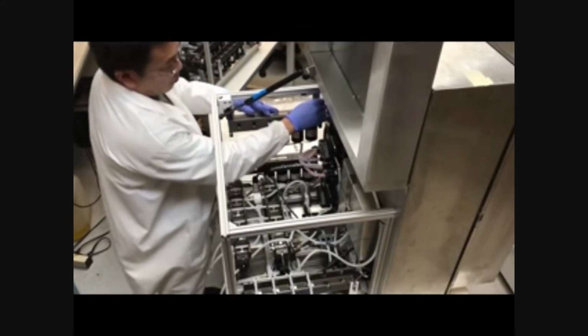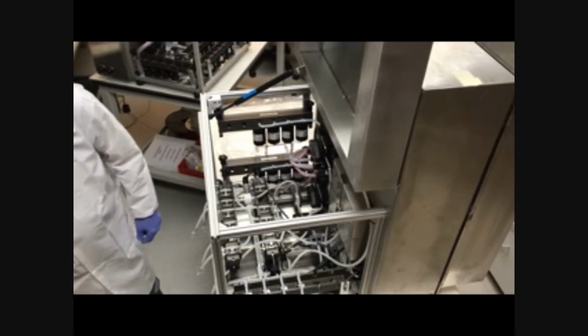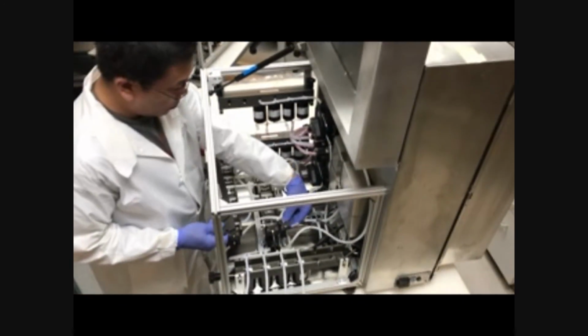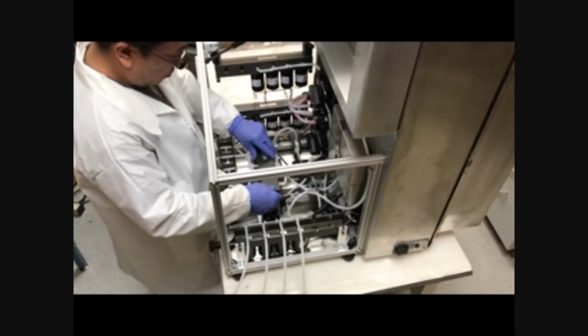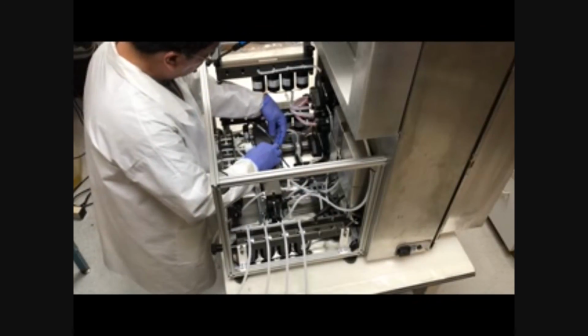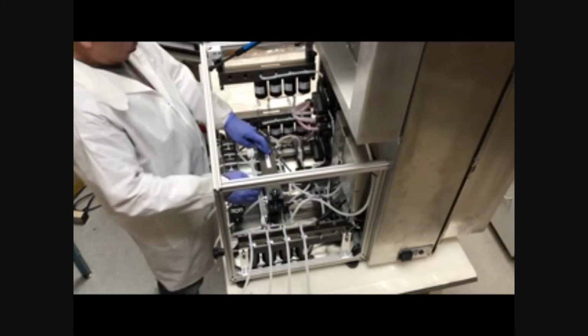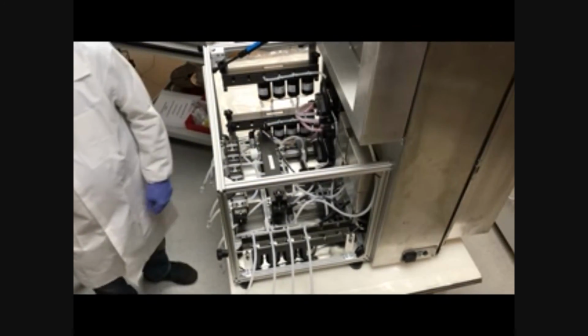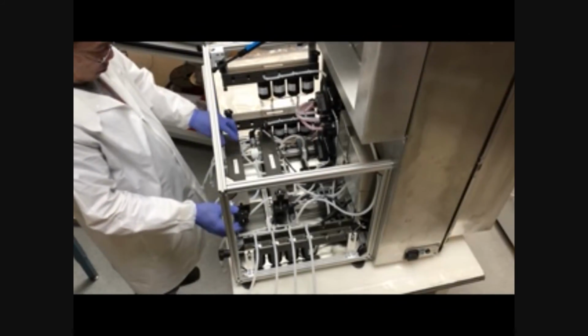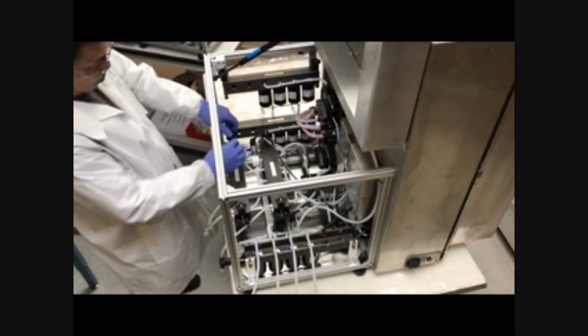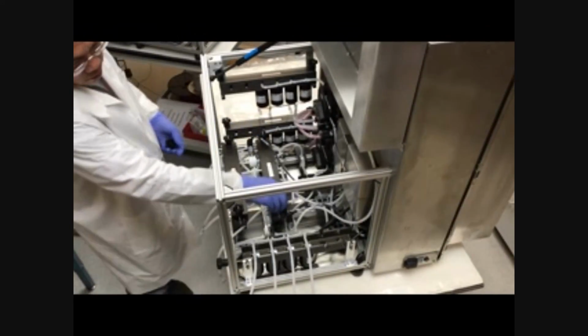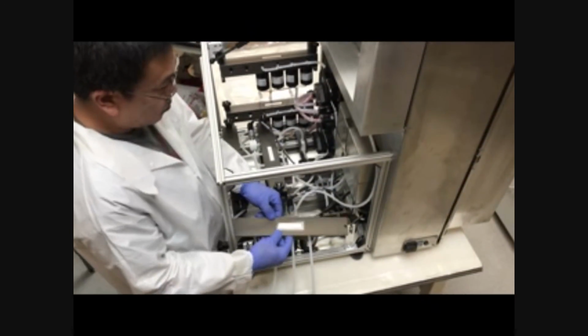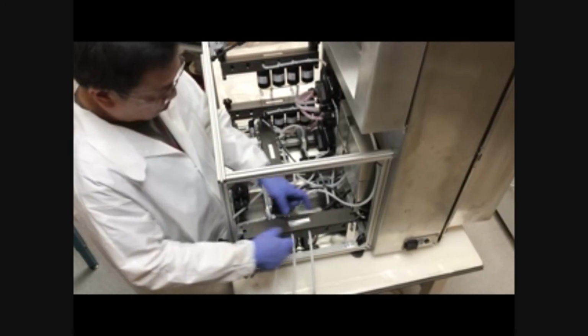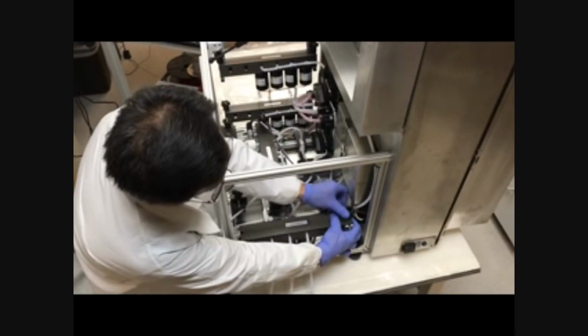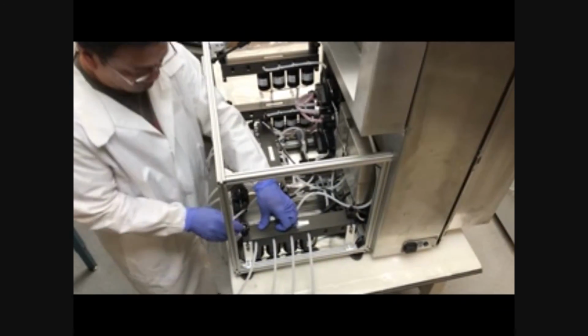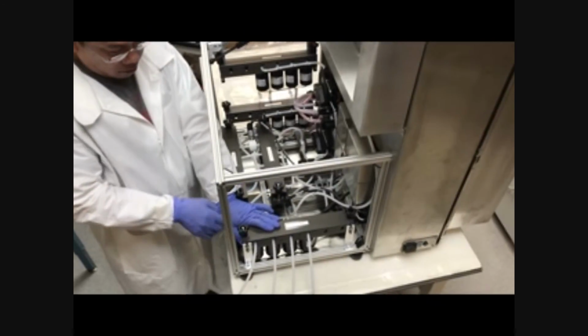You simply install the bar and hand tighten the screws, and then similarly go ahead and install the pinch bars for each of the column manifolds. There's a column, which means to the column, from the column, to the filter, from the filter, the air eject, and so there are two sets of pinch bars that you install, which is what he's doing. Again, you hand tighten them, and then you install the pinch bar for the fraction valves. Again, very simple procedure. It doesn't require the use of tools or anything like that. An ordinary lab scientist should be able to do the installation.